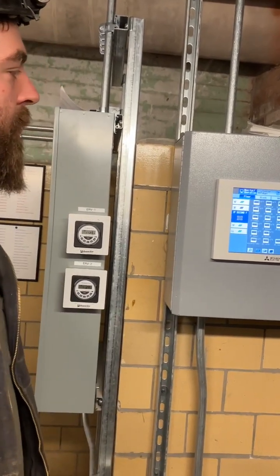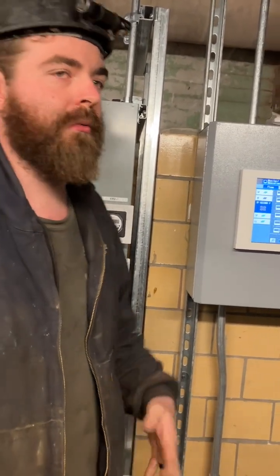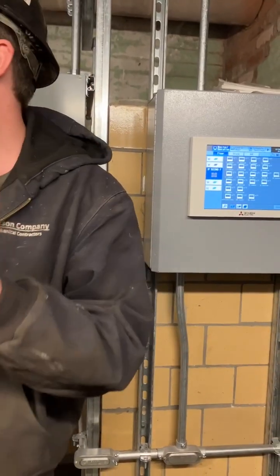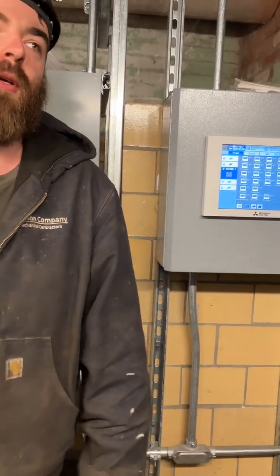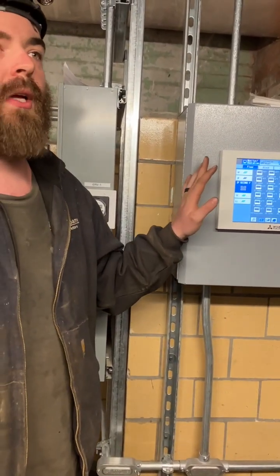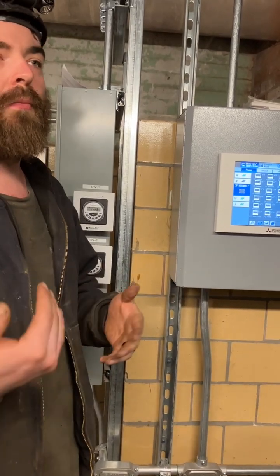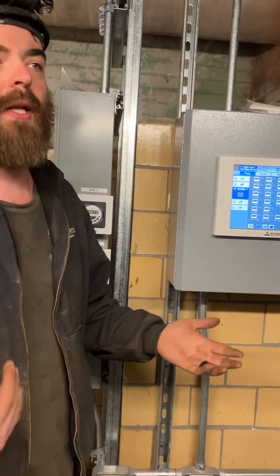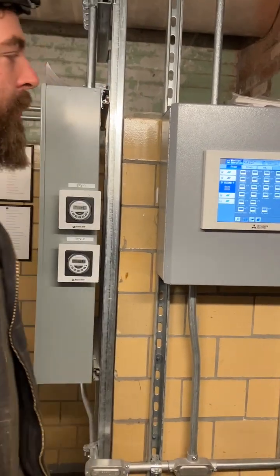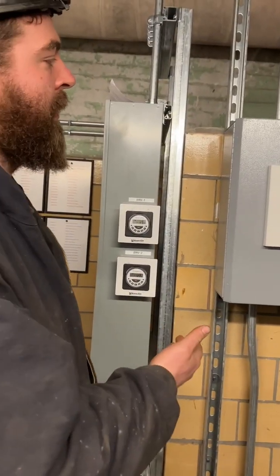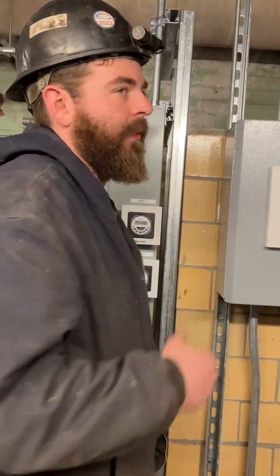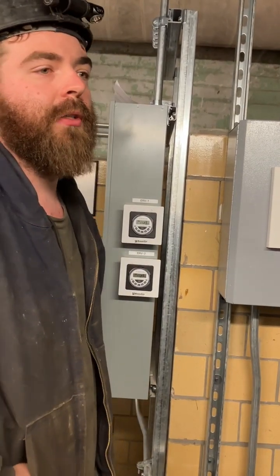But yes, in a pinch, say the boiler's totally gone, I don't know, a bus comes through and destroys everything, this will heat the building 100%, but you have to reprogram it on the Pelican front end to accept that stage. I wouldn't suggest running them like that though, it's better to have the gas first. It's much more cost effective and much easier on the equipment.